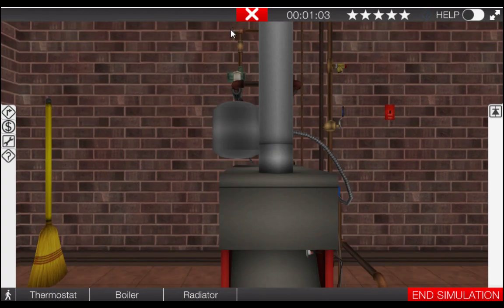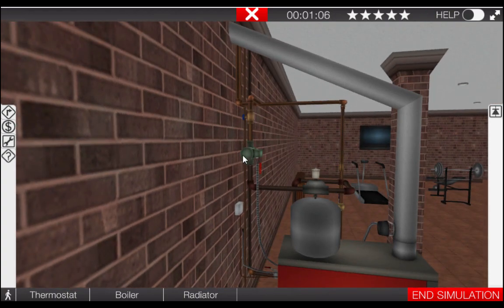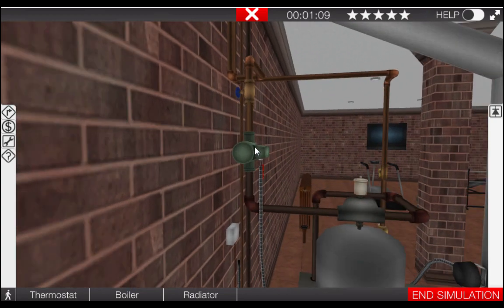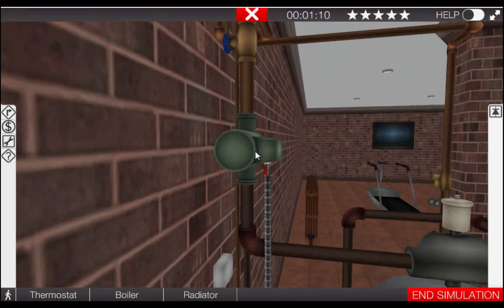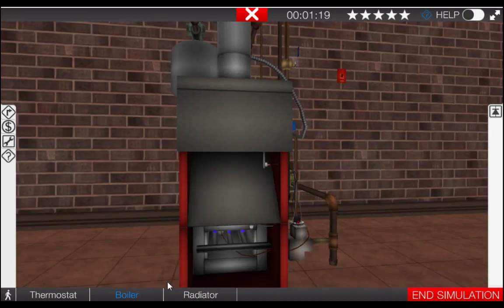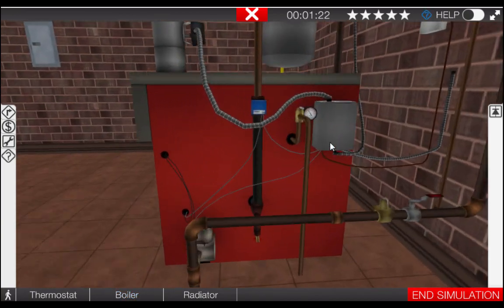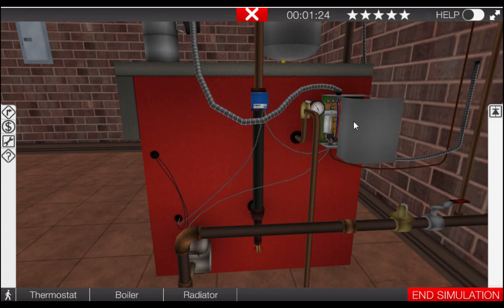Our next step is to go to the circulator pump to verify that it is operating. The circulator pump will have a graphic indicating that it is running. Here we can see there is no graphic shown on the circulator pump, indicating it is not running. This eliminates an air issue, meaning either the circulator or the combination aquastat is defective.